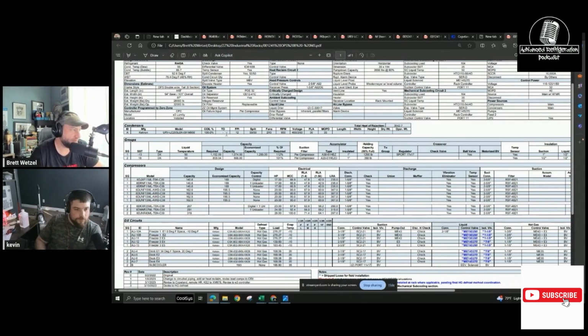So the other thing, this is going to make me a liar, because typically, for the condensers, it usually will give you a TD, right where it actually says TD here. And so you can figure out if the condenser is okay, if, like Kevin said, it hasn't been remodeled 6,000 times to Sunday, right? Making sure that someone hasn't kept adding, let's add a bigger compressor, let's add some more compressors. If it's a fairly new refrigeration schedule that hasn't been monkeyed with, or the date is up to date with what it originally was, you should be all right. But for the condenser TD, I can look at this, and if it says 10 degrees, anything above 75 degrees ambient, it should be able to maintain that 10 degrees. And what I mean by that is, whatever the ambient is, let's just say it's 90 degrees outside. If it has a 10 degree TD, theoretically it should be running about 100 degrees saturated condensing temperature on the discharge liquid side of the pressures.